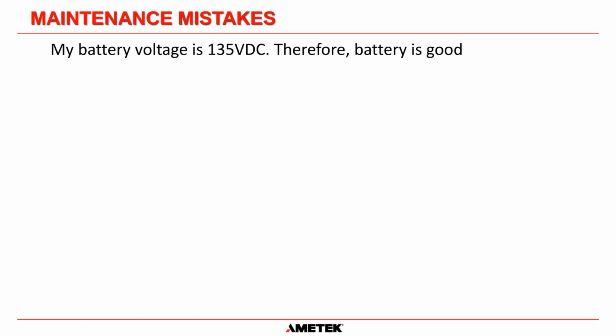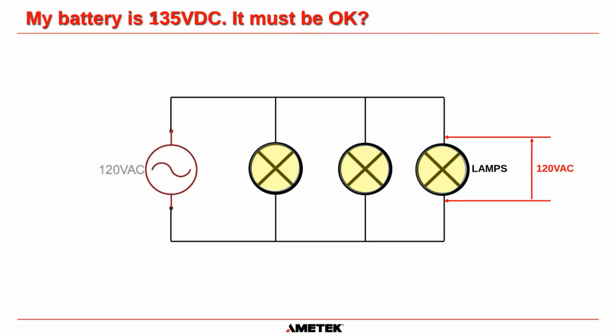The next one is, my battery voltage is 135 volts DC, therefore my battery is good. Oh, how wrong can you be? The float voltage of your battery gives you absolutely no indication of the state of charge or health of your battery. And here's a good example why. So we have our 120 volts AC going into our house, and we have a circuit that has 3 lights in our house. If you measure across each of these lamps in the fixture itself, you will measure 120 volts AC. They're all in parallel.